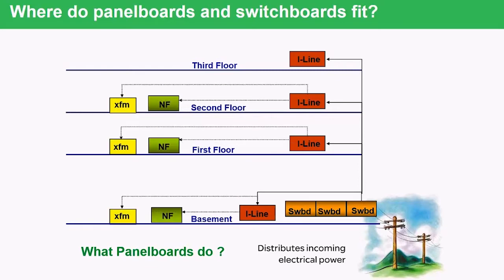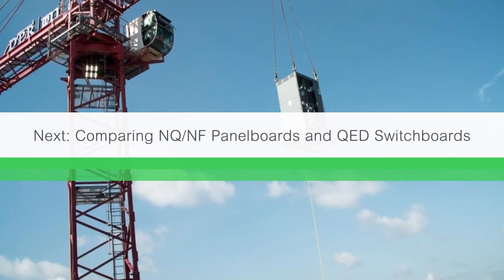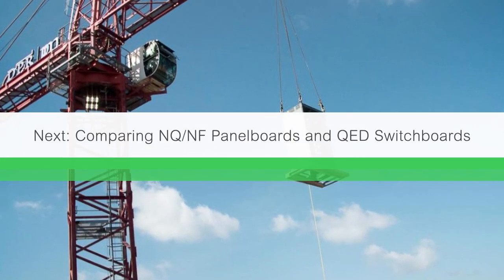From there, we can take the 480 volts and run it to a transformer — a general-purpose dry-type transformer — and convert it down to something like 208Y/120 for lighting, computer machines, and office machines. All of this can be done from the switchboard to a panel board, and we can also feed a transformer from an NF panel board.